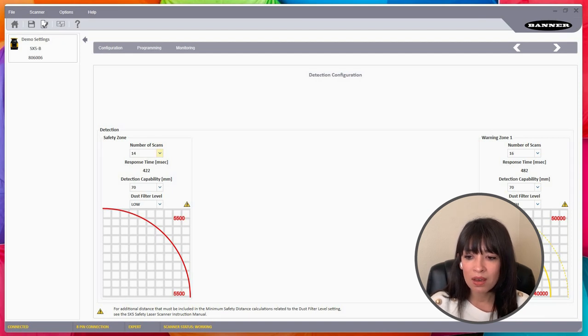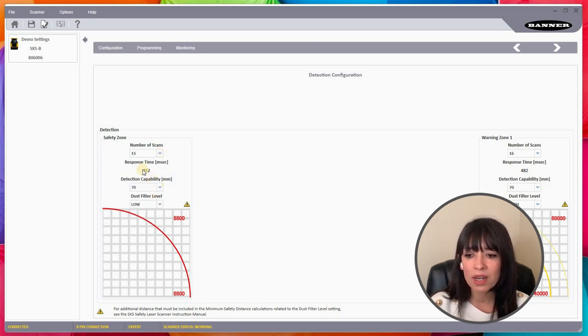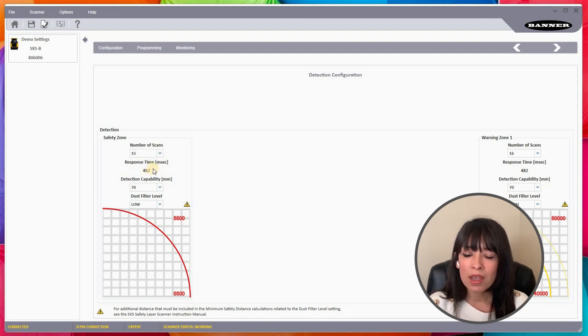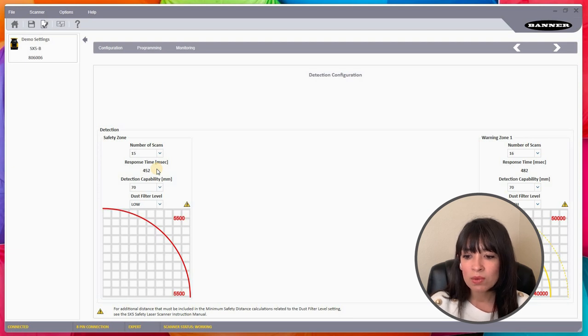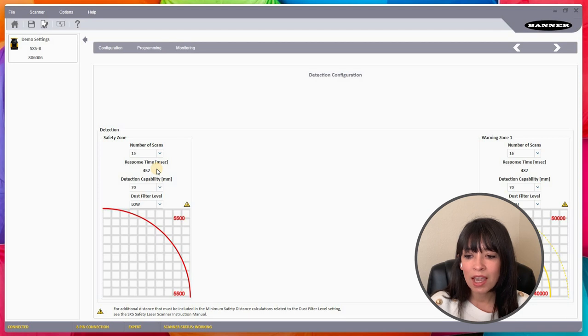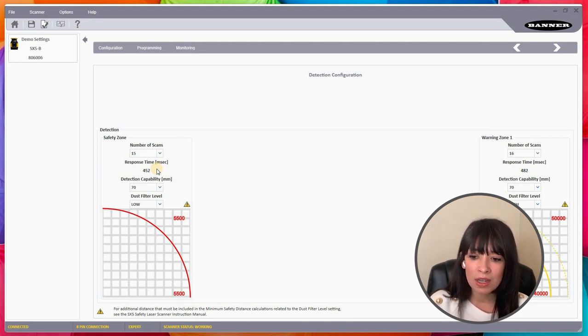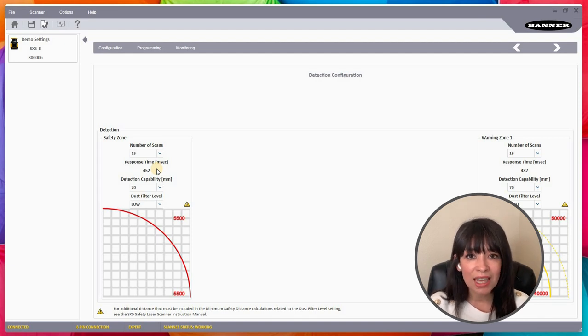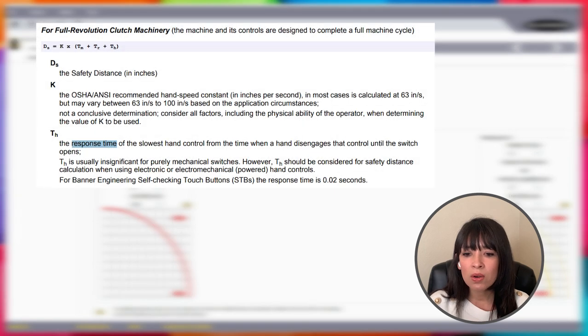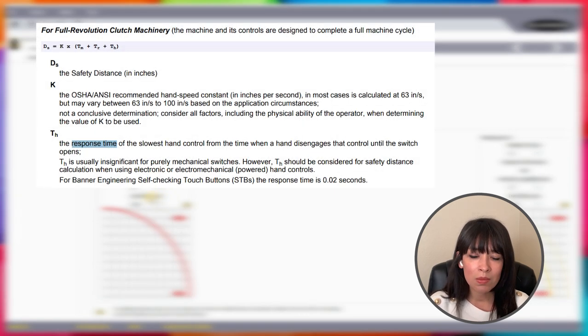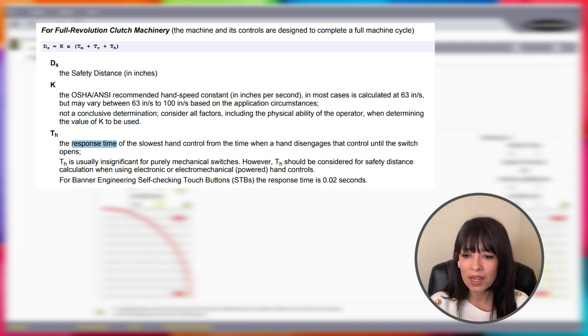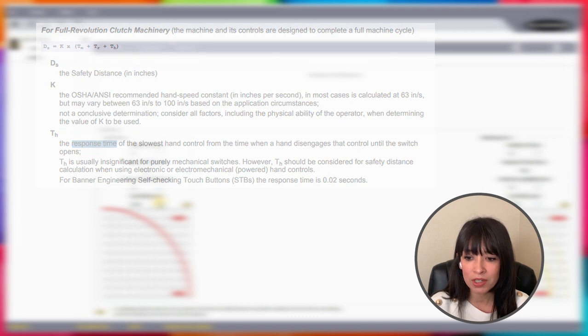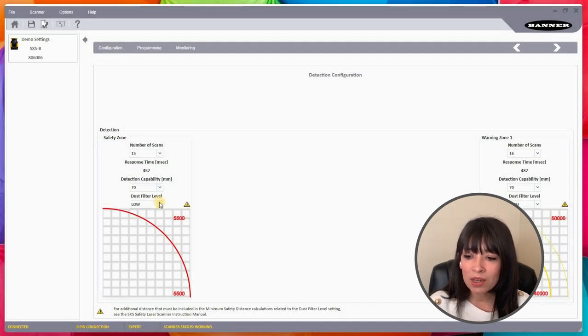We have the number of scans, and what this does is it tells you how many scans it needs to have before it actually gives you an alarm. As you increase this number you see that the response time will keep going up. This is a number that you have to watch out for depending on the risk assessment that you did on your machine. There's actually a safety calculation that you have to work in to figure out how fast your application response time needs to be. Some safety people know that, and we do provide that information.